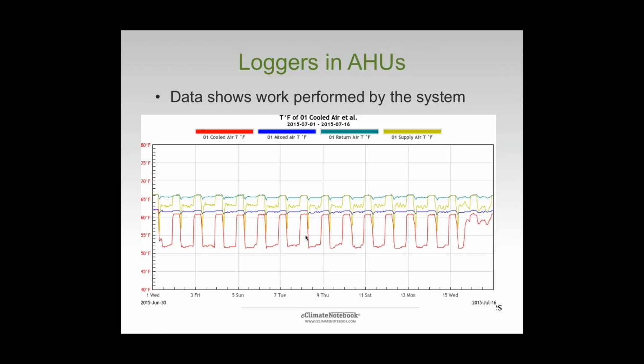And when we get something that looks like this at the end of the day, multiple different plots on a graph, and we realize that, all right, if I follow my return air, this nice kind of greenish bluish color here, well, that stays fairly steady. When the return air comes in, it gets mixed with outside air to create the mixed air condition. So that mixed air is now cooler than the return air. That tells us that we're using definitely some outside air, and presumably that the outside air condition is a little bit cooler down here, depending on where we're at. So we have a mixed air condition, and now we're going to say, all right, after the mixed air, we go to the cooled air, and here we are.